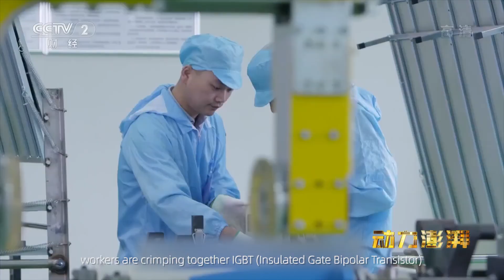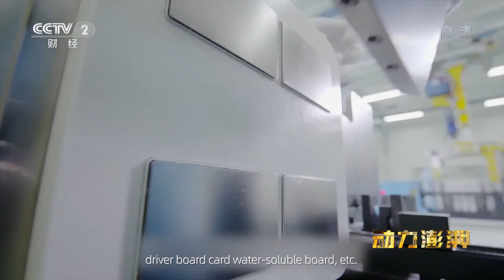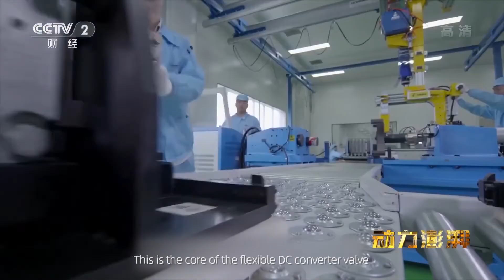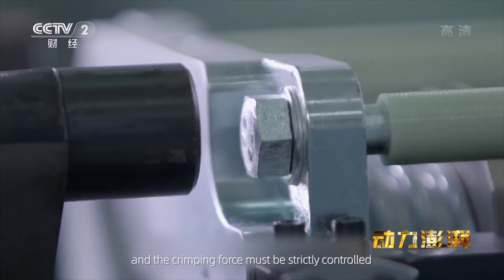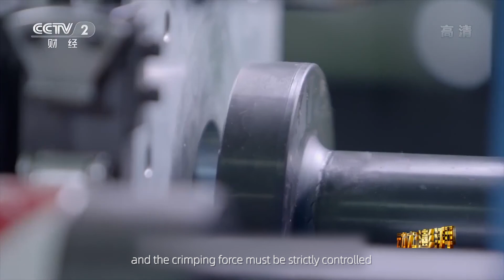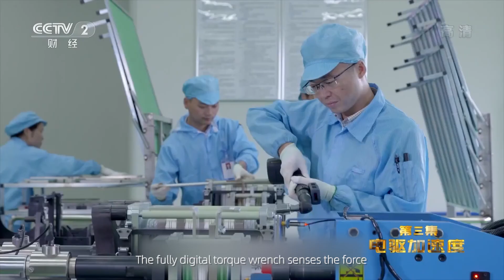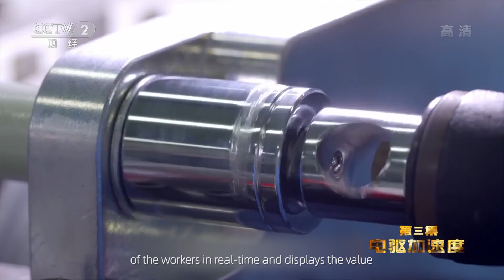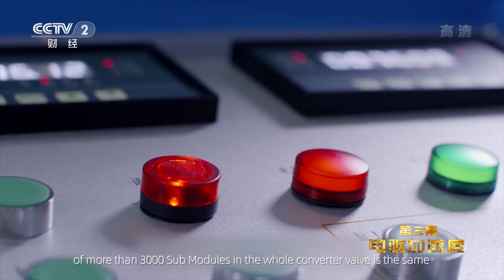In the 100,000 grade cleanliness workroom, workers are crimping together IGBT, driver board card, water-cooled board, etc., to combine into a complex flexible DC module. This is the core of the flexible DC converter valve, and the crimping force must be strictly controlled. The fully digital torque wrench senses the force of the workers in real time and displays the value on the monitoring screen to ensure the bolt torque accuracy of more than 3,000 submodules in the whole converter valve is the same.